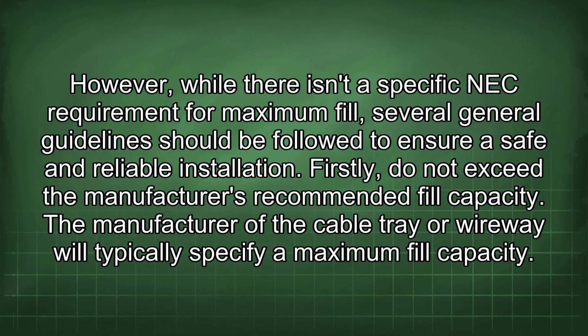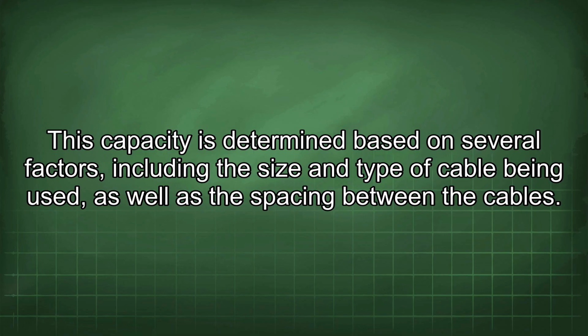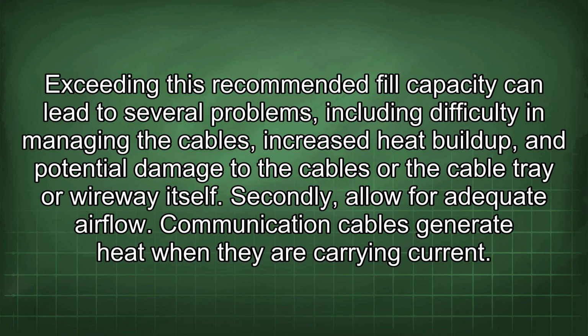The manufacturer of the cable tray or wireway will typically specify a maximum fill capacity. This capacity is determined based on several factors, including the size and type of cable being used, as well as the spacing between the cables. Exceeding this recommended fill capacity can lead to several problems, including difficulty in managing the cables, increased heat buildup, and potential damage to the cables or the cable tray or wireway itself.